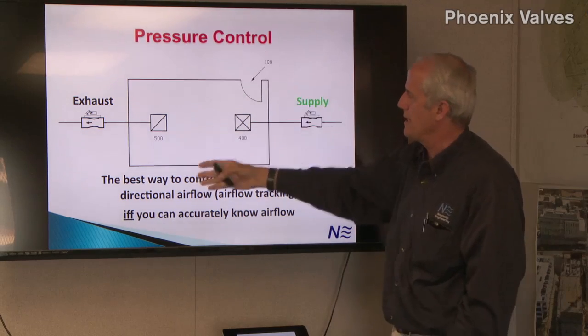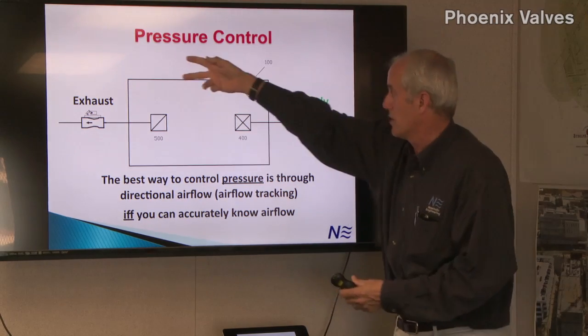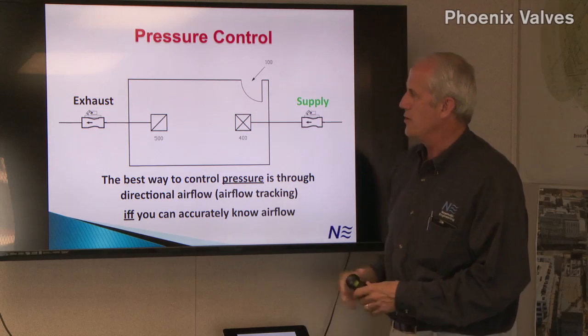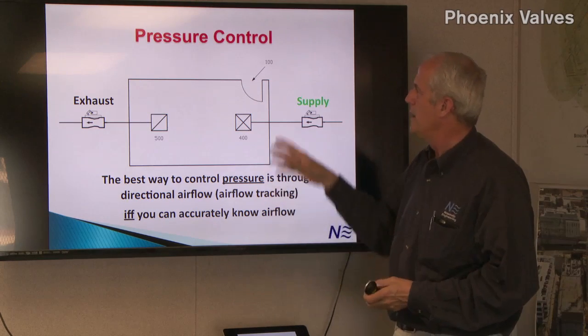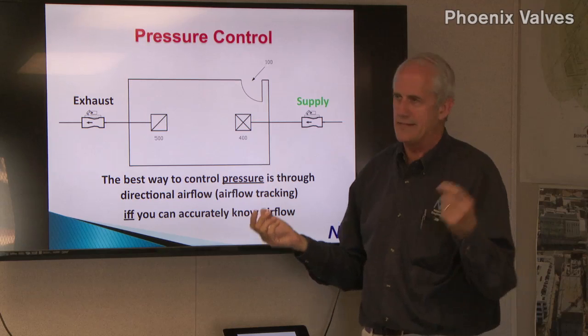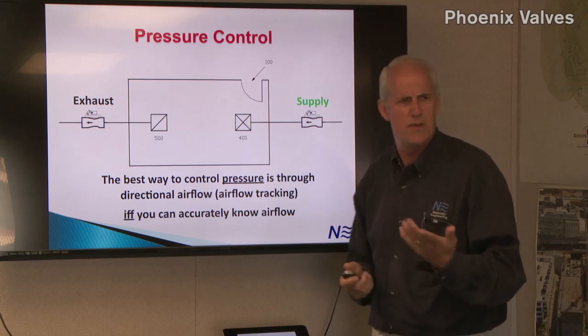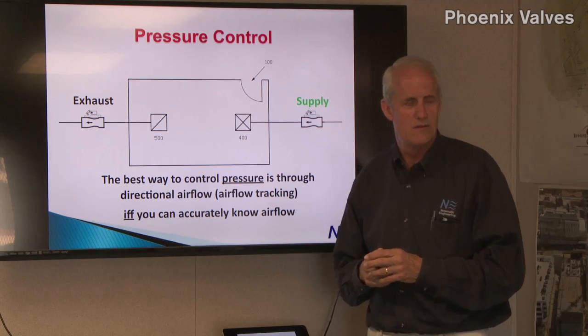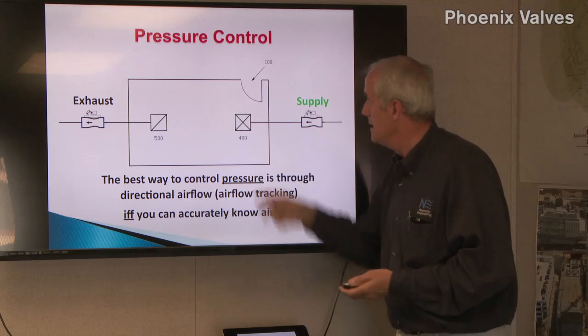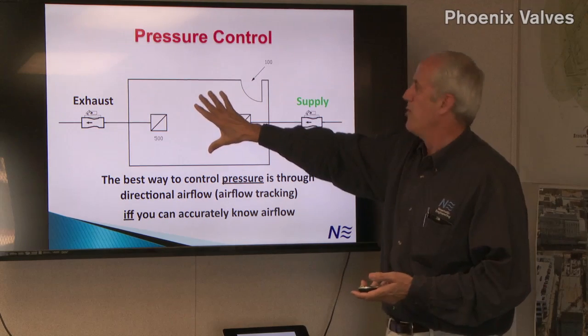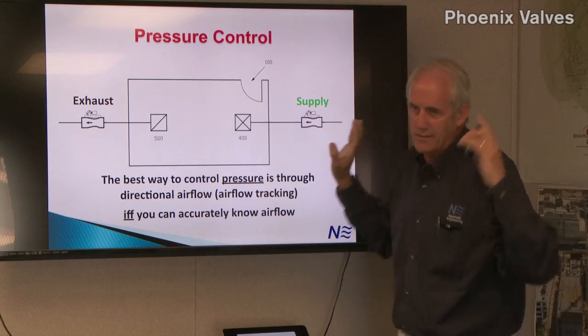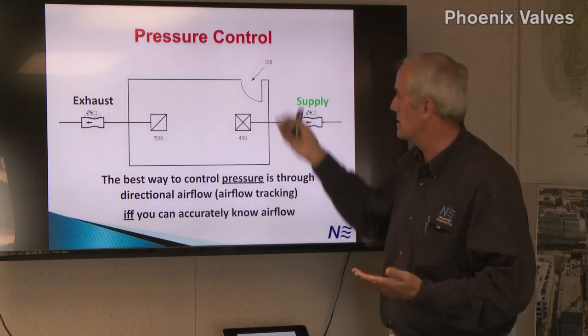So you will get a pressure relationship between the corridor, which is typically out here, and your holding rooms or procedure rooms, whatever they are, when the door is closed. And you balance to that, and that's what your balancer did on this job. Who balanced this job, do you know? Balance America. Okay, good. So the balancer might make this room minus 0.03 or something like that. Whatever they went for, we're going to hold that pressure when the door is closed.